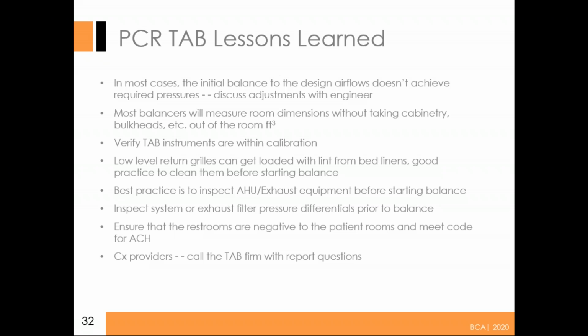And the other thing, especially in isolation rooms, is your restrooms. Typically, all isolation rooms a lot of times have restrooms in them. You always need to make sure those restrooms are negative, typically tied to that exhaust system, and you're meeting your design air changes per hour. So those are some of the things that we really look for: making sure those restrooms are good, making sure they're negative, and making sure your differential pressures are correct. And also, one of the main things is making sure your differential pressure monitors for the users are reading accurately. And one of the better things to do is if you've got a set point, like a 0.1, you always want to move that up a little bit so you don't have nuisance alarms. That's the worst thing that you can have.